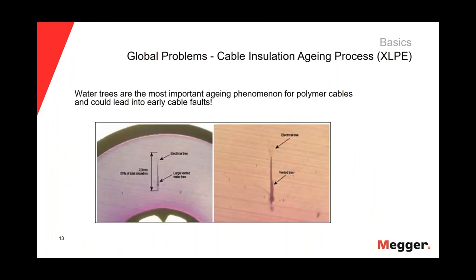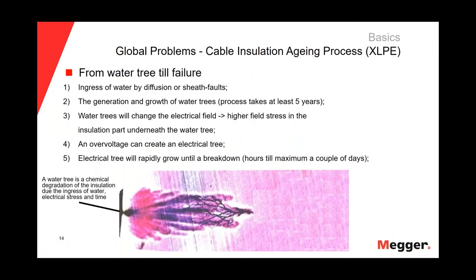In the case of XLPE insulation, the main driver — the most important phenomenon — is water trees. Water trees are developed in the insulation as follows: it all starts with the ingress of water by diffusion or jacket faults. For that reason, it's very important that when we pull the cable, we don't put holes in the jacket, because those perforations will permit the ingress of water into the insulation.